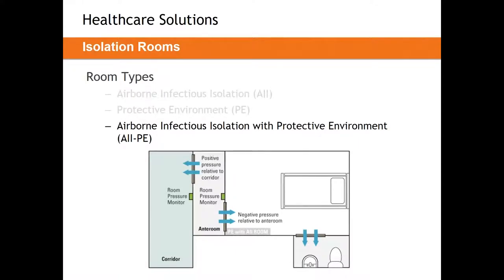The third type is the combination: airborne infectious isolation with a protective environment. This is the same as an AII room, but with a positive anteroom connected to it. The patient space is negatively pressurized, while the anteroom is positively pressurized and acts as a barrier between the corridor and the AII room, ensuring only clean, fresh, filtered air infiltrates into the isolation space.